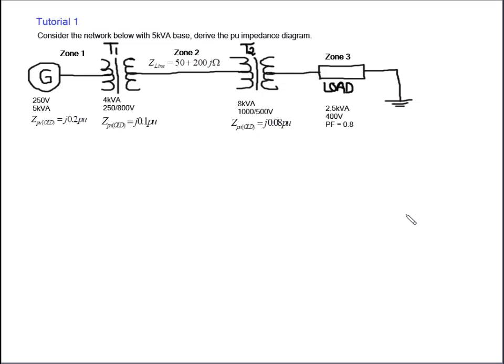So based on that, you have to know your short circuit current on every stage of your network. That way you will be able to provide adequate protection based on the short circuit level. So the diagram we have in front of us is a network diagram that is made of a generator, transformer one, a line impedance, transformer two, and the load connected.